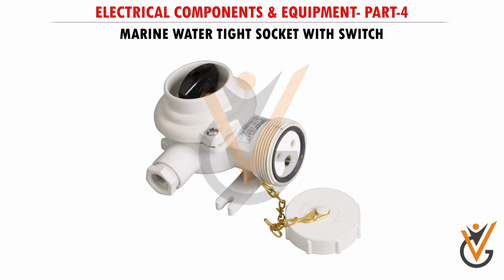Wall-mounted marine sockets have an insulated base molded with brass or plastic materials. Used widely on board ship for utility purposes, for example for connecting extension lights, vacuum cleaner, blowers, etc. Voltage used is 115 volts or 220 V. These are made for 5 amps and 15 amps load.